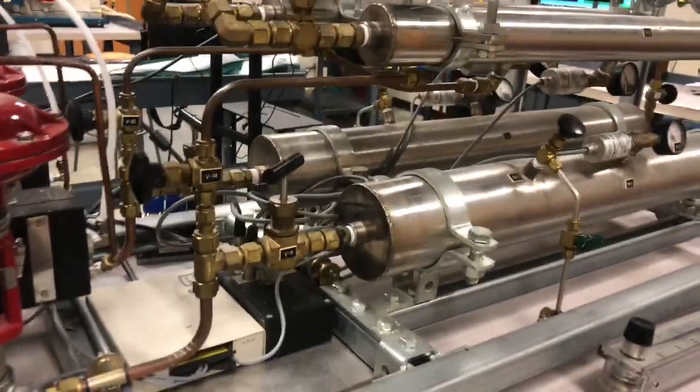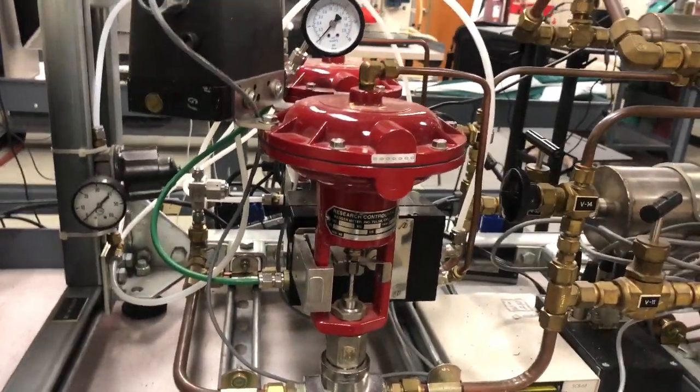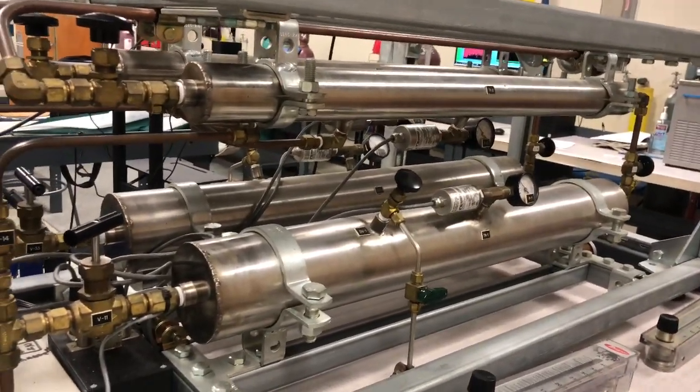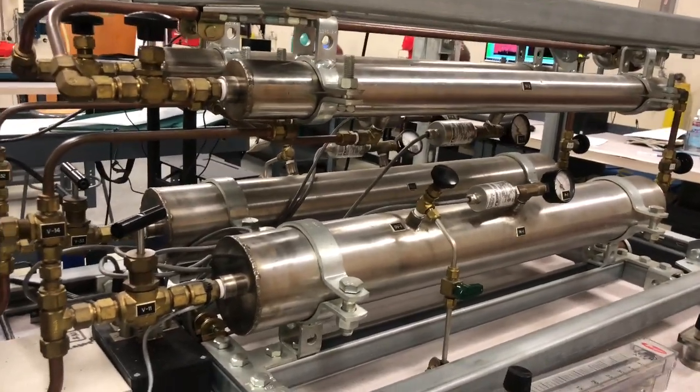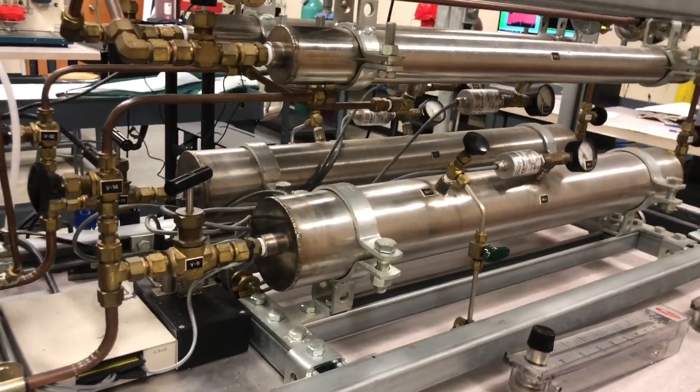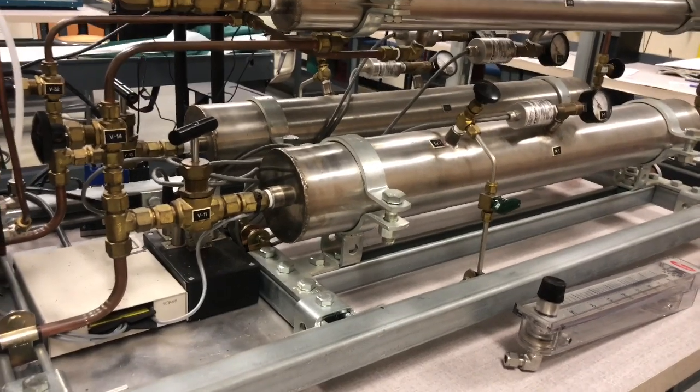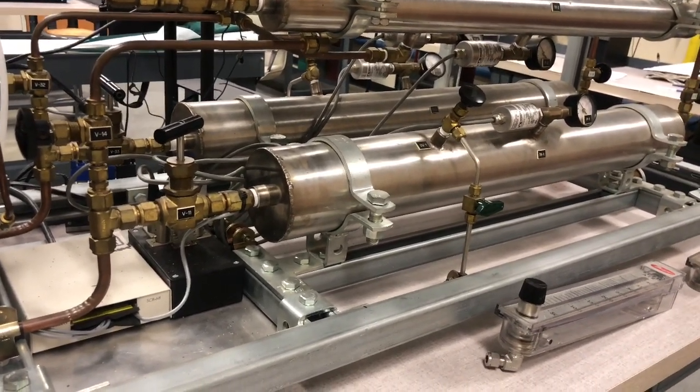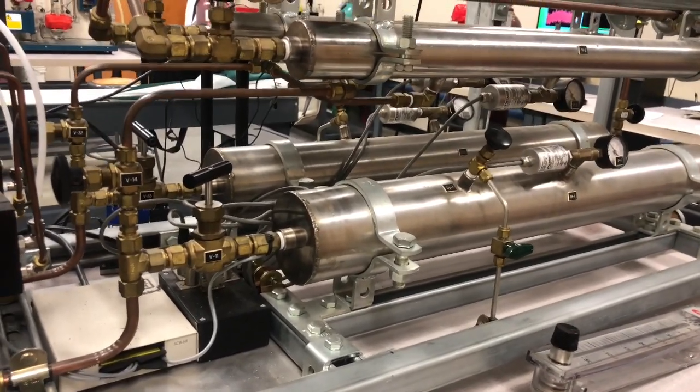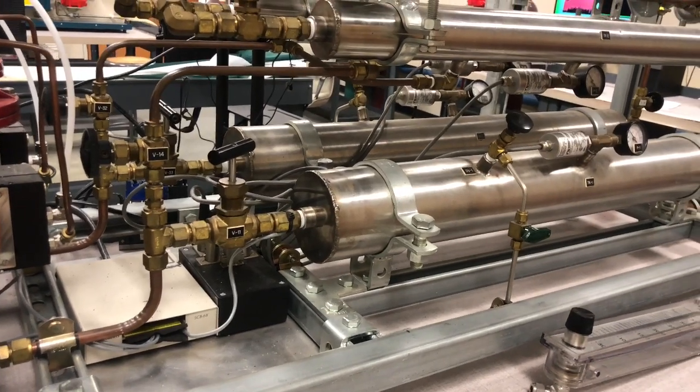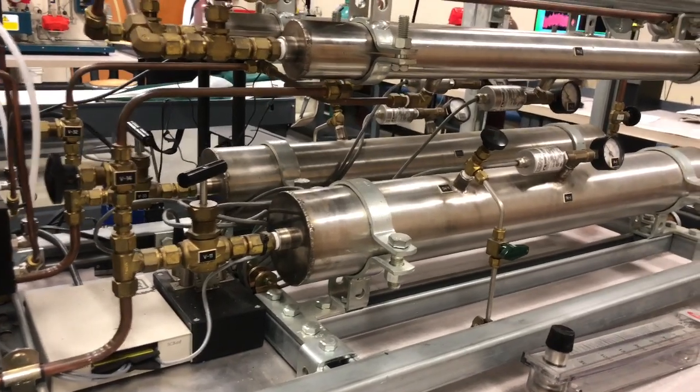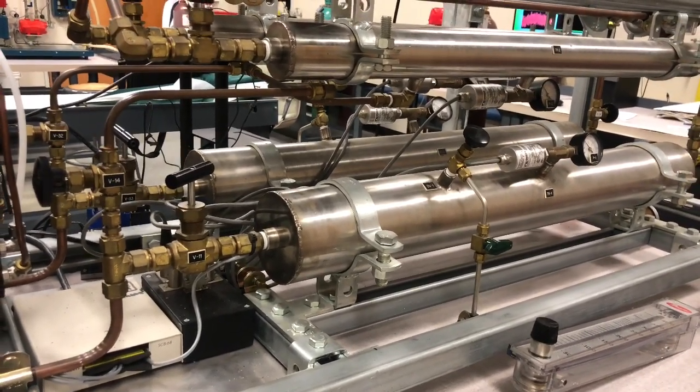Now, for this setup, I believe we're using 0 to 5 volts. So 0 might be all the way closed in the valve, 5 may be all the way open. The same thing for pressure. There's a pressure range. So you measure that 0 to 5 volt signal and then interpret, oh, is that 40 psi? Is that 50 psi? A lot of times in industry, they use 4 to 20 milliamps. Because if you're working around high voltage or big motors that have electromagnetic fields, they can create spikes and noise in voltage signals, but they don't affect the current signal.